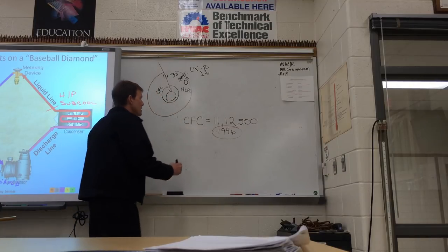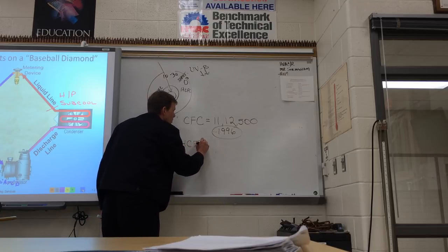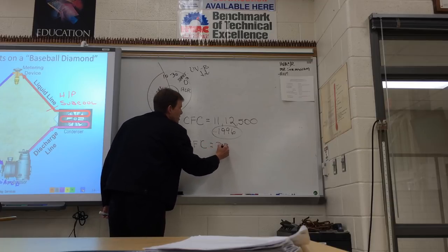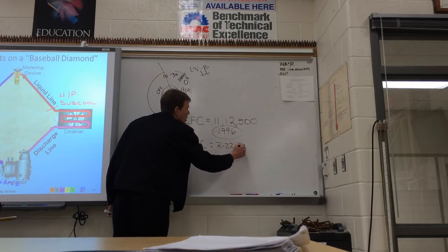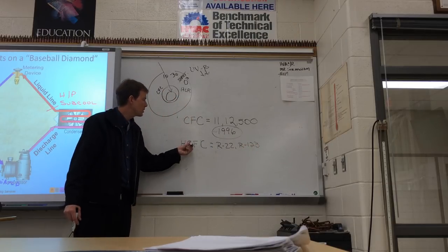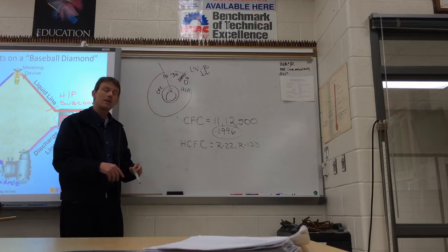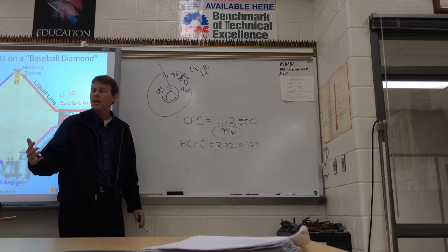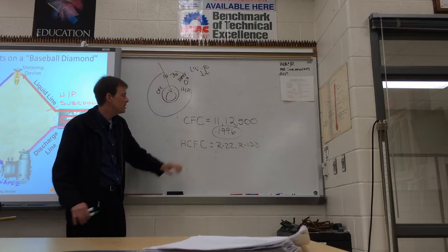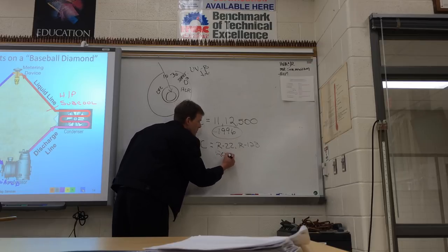And then that just left HCFCs, hydrochlorofluorocarbons, which was like R22 and R123. Which these two refrigerants have not only chlorine, fluorine, and carbon but they have a hydrogen component which made them less stable, less likely to reach the atmosphere. So we can continue using these until 2020 which is just only a few years away.